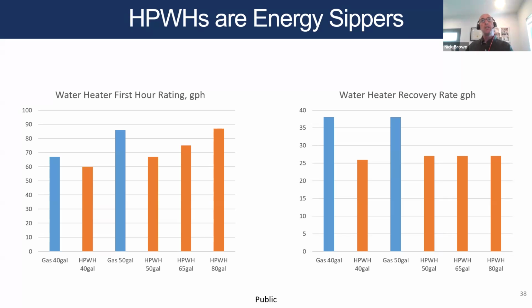So we say upsize the tank of a heat pump water heater compared to the size tank you would have used if gas, 1 or 2 notches. This is because the recovery rate of a heat pump water heater is down around 25 gallons per hour, whereas a gas burner is bigger. Okay, more like 37.5 is what we've got on this chart. But I'm here to tell you that just like we've oversized our HVAC heaters, our furnaces, we've oversized our gas water heaters too, in most cases. And the extreme case is a gas tankless water heater.